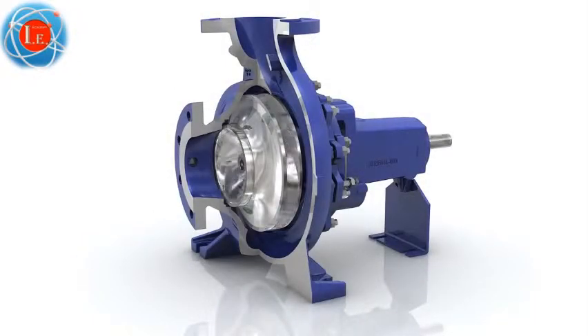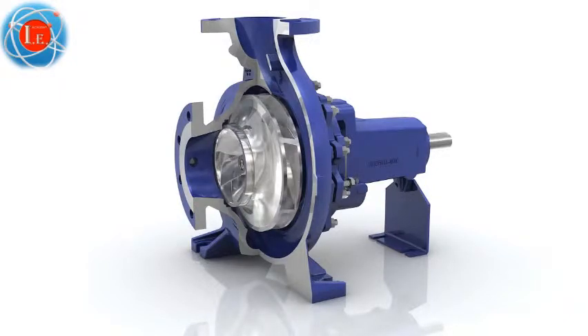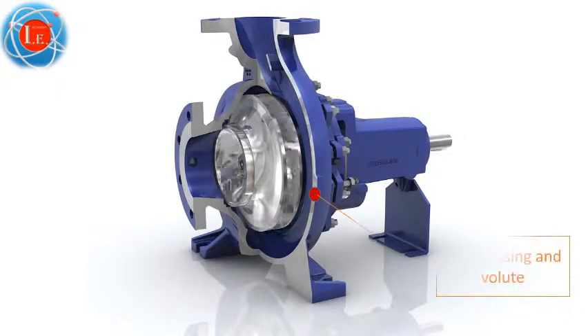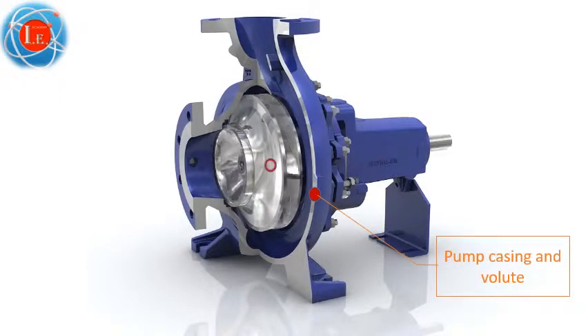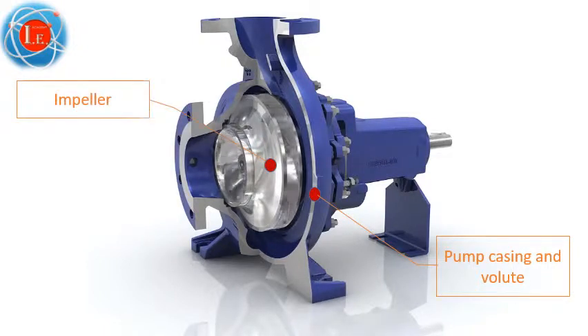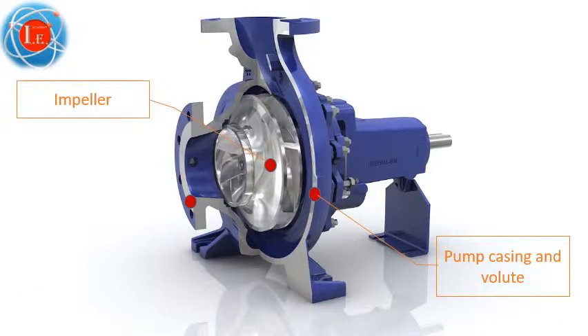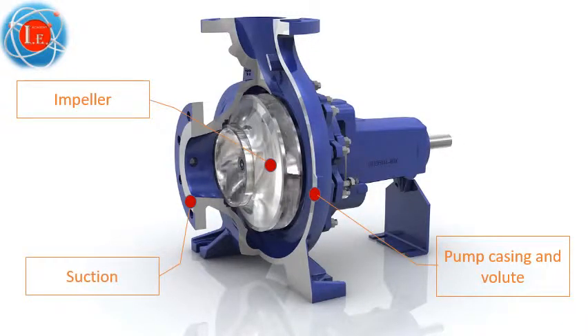The pump casing acts as a pressure boundary and contains channels to properly direct the suction and discharge flow. The pump casing has suction and discharge penetrations for the main flow path of the pump, and normally has small drain and vent fittings to remove gases trapped in the pump casing, or to drain the pump casing for maintenance.